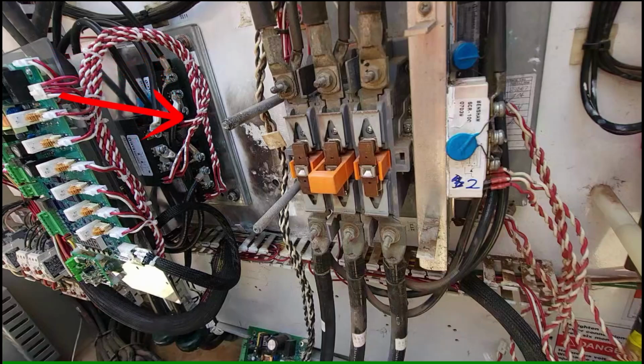So we can gently apply power through these 3 legs to the motor and get that motor to slowly spin up. And when I say slowly, this is still happening in a matter of seconds, okay? This is slow in relation to this thing that just slams closed and has to haul ass, okay? Slow in relation to that. This is instantaneous, this is slow. That's what I mean as a perspective. This isn't going to take several minutes to accomplish. This is going to take a few seconds at most, if not 1 or 2 seconds.